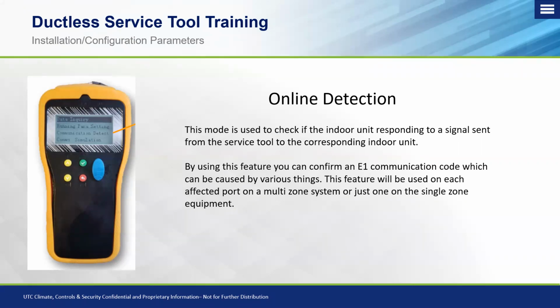Of course, we want to start simple. We don't want to start crazy and start thinking algorithms and all this other crazy stuff that's causing E1. We start basic. So this feature is going to be used on each affected port in a multi-zone system, or if you're dealing with a single zone system, just that one particular indoor unit that's causing the E1 code.